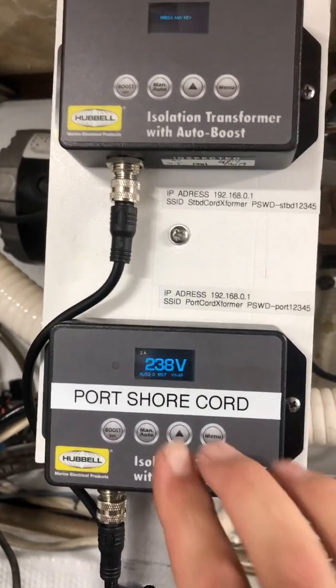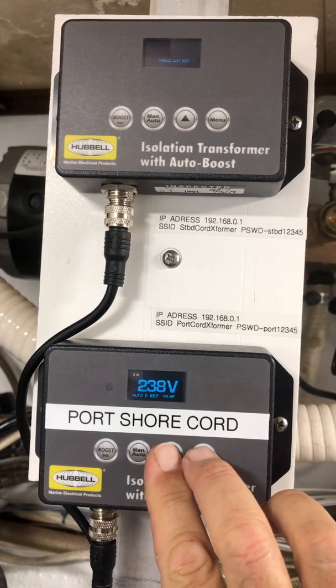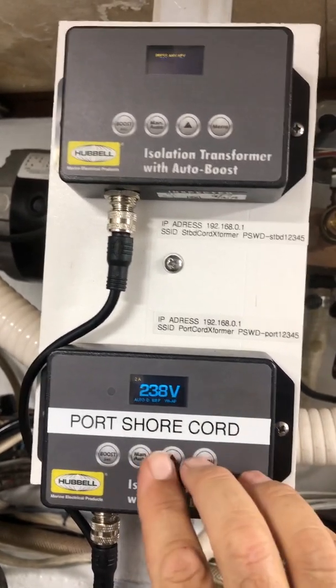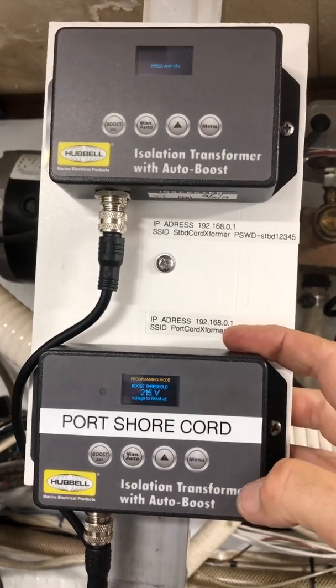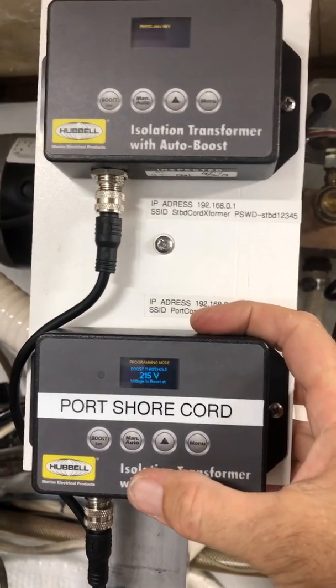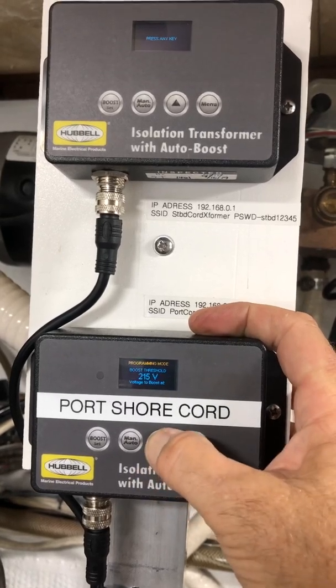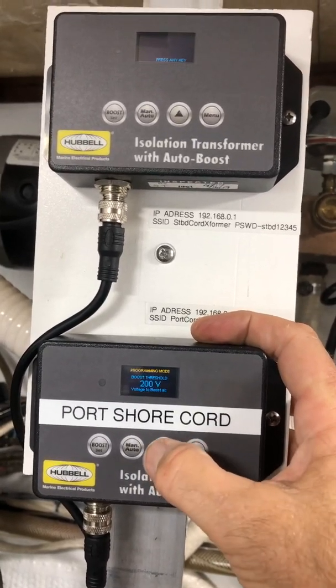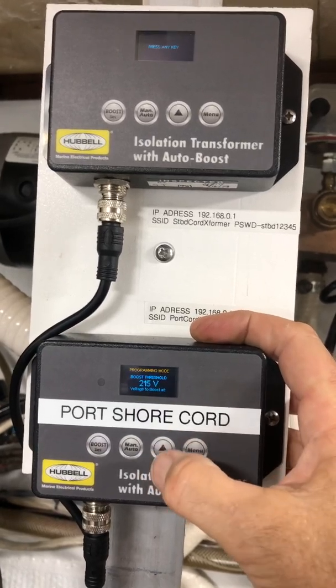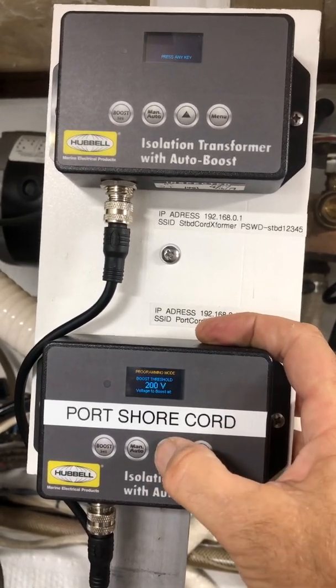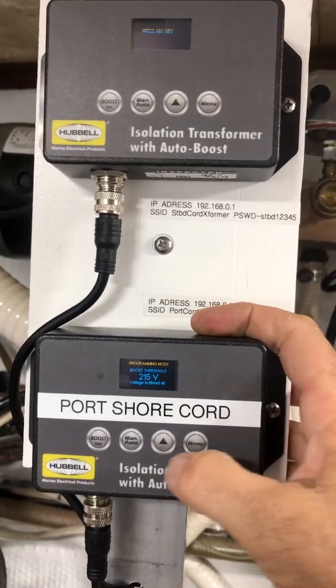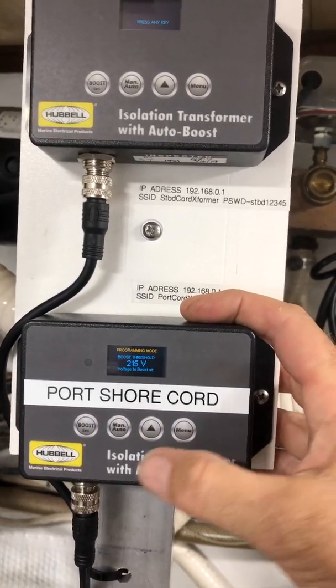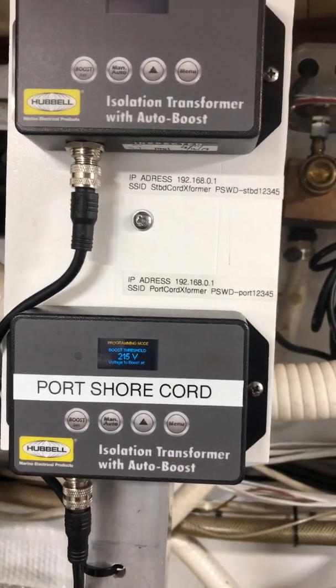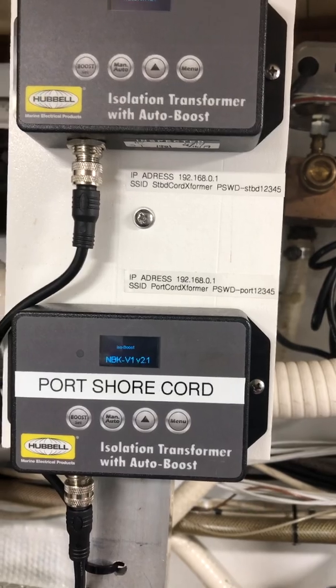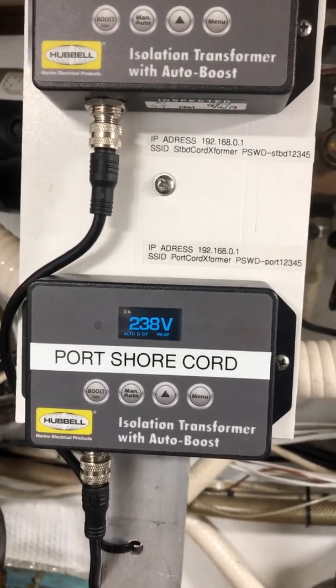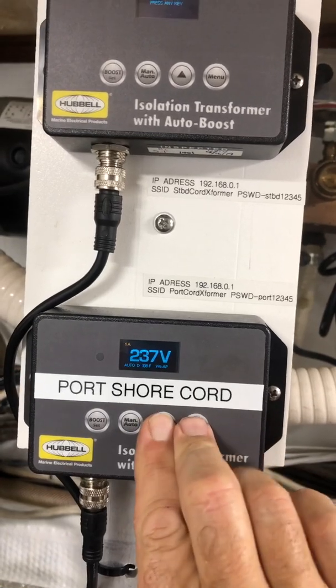To change that, you'll enter the programming mode by pressing menu and up, and this puts you into the programming mode. You can change the boost threshold by pressing the up arrow key, and you'll see it cycles through these voltages. We're going to leave it at 215. If you want to save this value, you have to press the boost key, and you will see the Hubbell icon appear, and the unit restarts.